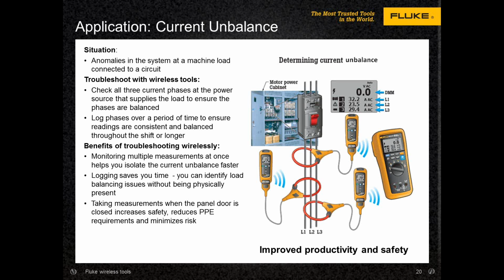So the conductor doesn't have to be in the center, and if you have another conductor on the outside of the loop, let's say with current going through it with magnetic fields, that's not really going to interfere, right? Right. Nice. Very nice. So again, the wireless stuff helps you. In this case, when we're talking about current unbalance, we're talking about a 3-phase situation where 3 modules can help you do that. You can see everything all at one time. Typically, in conventional methods, you make one measurement at a time, and then you have to calculate your unbalance.